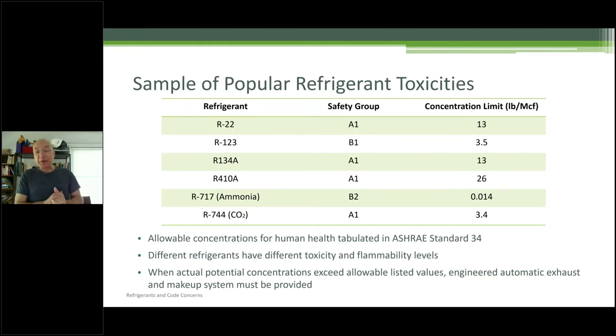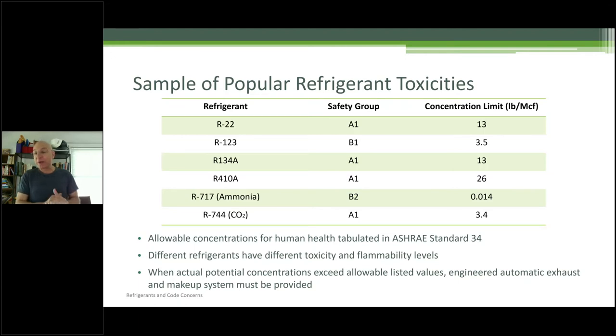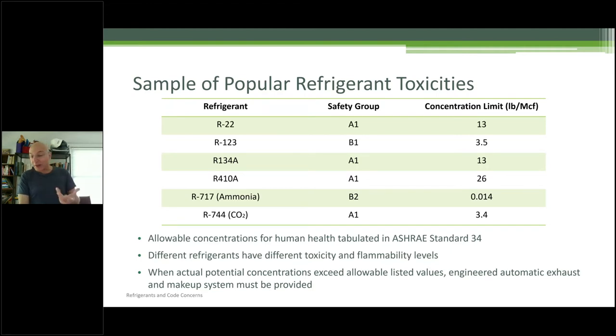CO2 — R744 — is an A1. Obviously CO2 is not flammable and is considered non-toxic. But the concentration limit is much lower than 410A — it's 3.4 pounds per 1,000 cubic feet. So that's something to worry about with the introduction of new machines running on CO2. All refrigerants are listed in ASHRAE 34 with their different toxicity and flammability levels.